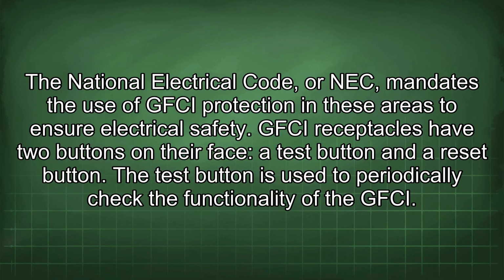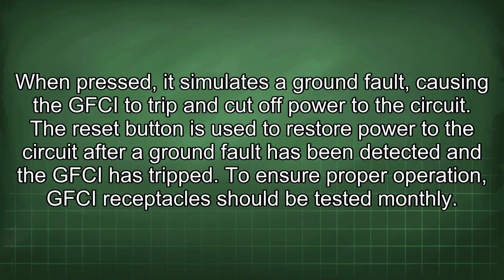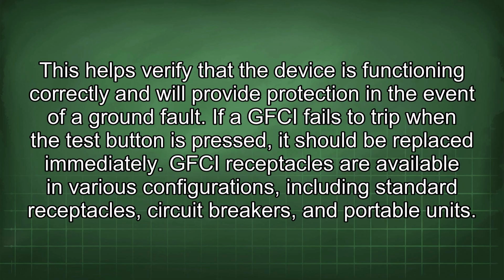ensure electrical safety. GFCI receptacles have two buttons on their face, a test button and a reset button. The test button is used to periodically check the functionality of the GFCI. When pressed, it simulates a ground fault, causing the GFCI to trip and cut off power to the circuit. The reset button is used to restore power to the circuit after a ground fault has been detected and the GFCI has tripped. To ensure proper operation, GFCI receptacles should be tested monthly. This helps verify that the device is functioning correctly and will provide protection in the event of a ground fault. If a GFCI fails to trip when the test button is pressed, it should be replaced immediately.